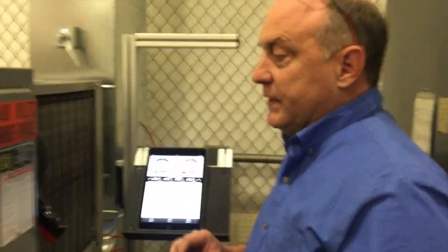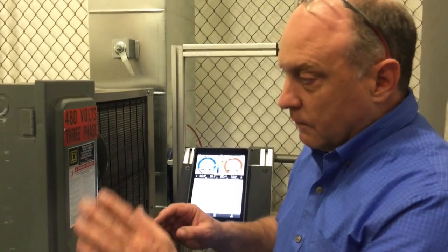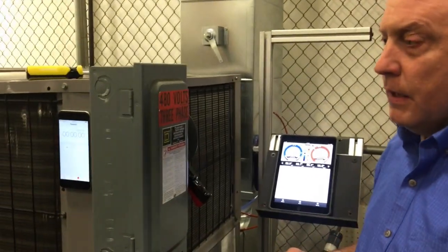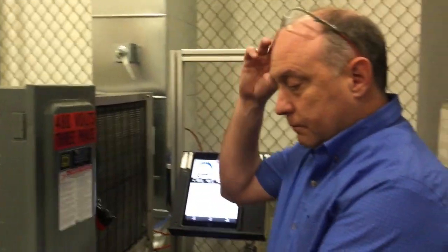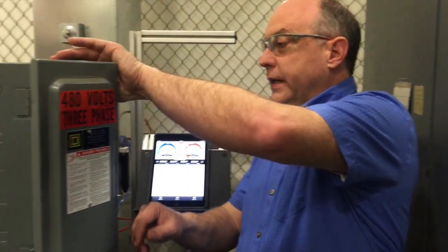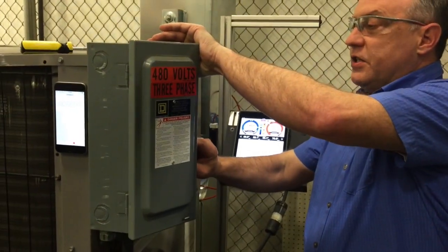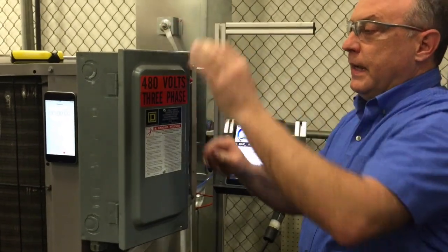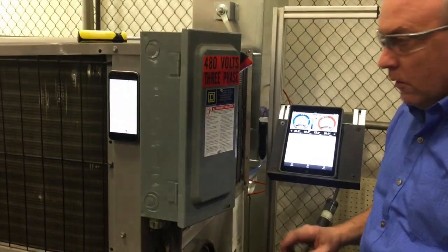So the next step in this is we're going to need to test power on the system. So I'm going to go ahead and hold the handle in a disconnect so that we can start the system up. And now I got the system started here. We're going to go ahead and get the meter and we'll make some electrical measurements.